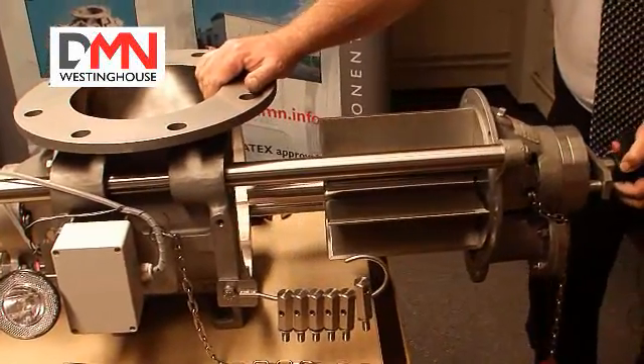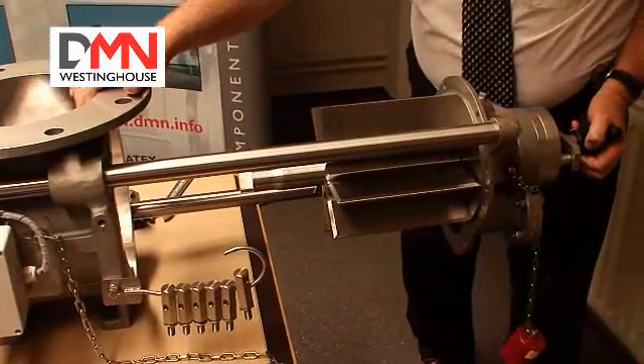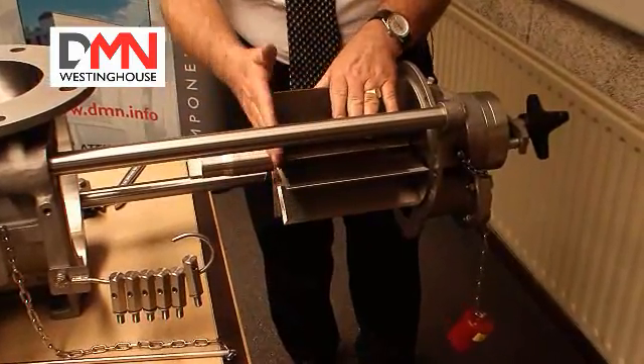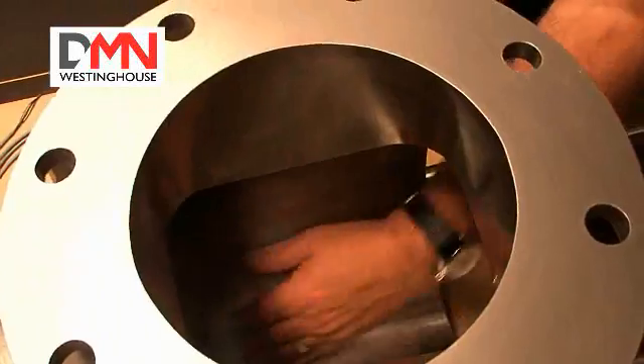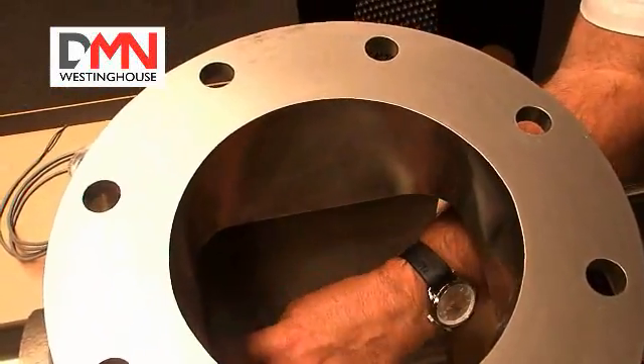Now I will extract both together. I now have the end cover and the rotor out of the valve. We can now clean the rotor further — we can clean this side of the rotor, the end cover, the bore, the drive dog, all the parts that need cleaning. We can also clean this shaft sealing arrangement.